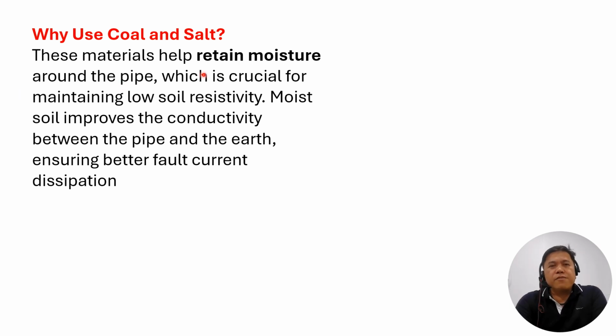These materials help retain moisture around the pipe. Moisture, remember this, is crucial for maintaining low soil resistivity. Moist soil improves the conductivity between the pipe and the earth, ensuring better fault current dissipation.